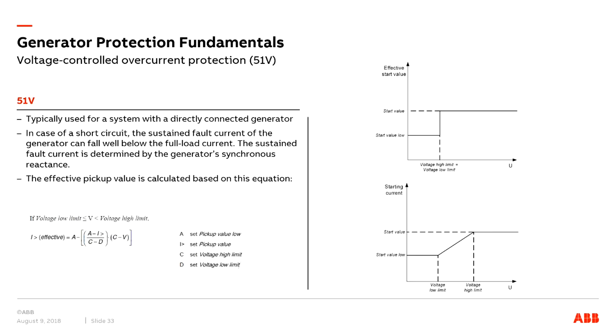We can achieve two characteristics here. One is called a step characteristic. This is achieved with the settings of the element with a voltage high limit equal to the voltage low limit. And then we can also achieve a slope characteristic when the voltage high limit and low limit are different. So the operating value will depend on the slope which we set, and it depends on the voltage of the generator as well. So the overcurrent pickup value varies according to the availability of voltage.